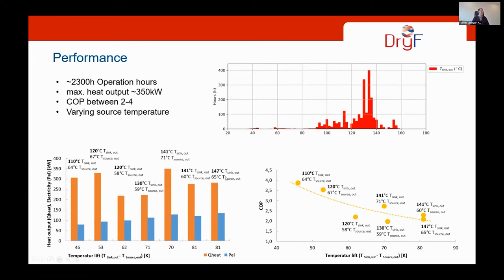In our complex heat recovery cycle system, we have a very fluctuating source temperature. You can see on these dots we have different temperatures at the source outlet, from 67 going down to only 58. So this is why the dots are a little bit spread around.